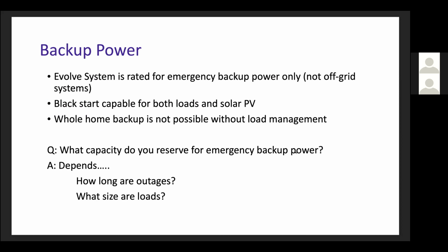So, quick review, backup power. The Evolve system is rated for emergency backup power only. It is not intended for off-grid use exclusively. It is black start capable for both loads and solar PV, meaning that it goes from being a current source that is synchronized to the grid voltage to being a voltage source when the grid is down. Whole home backup is not possible without load management.